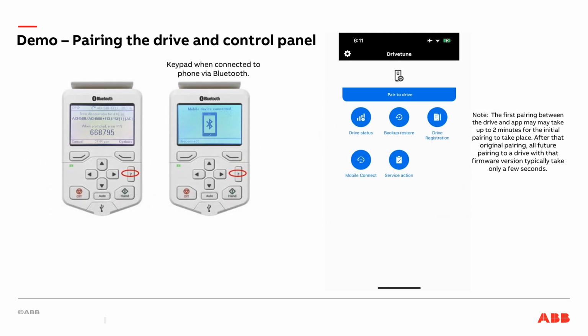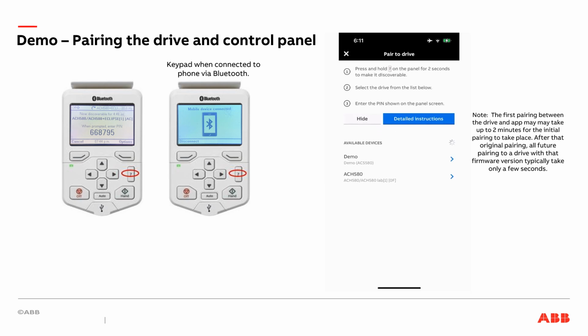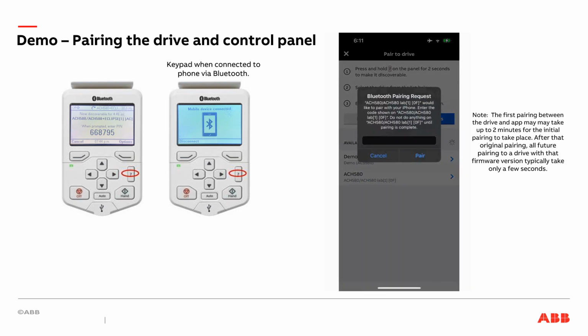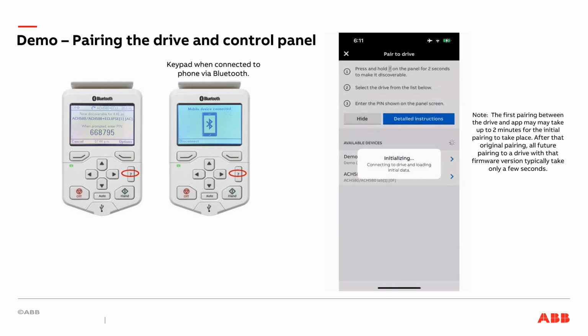After activating Bluetooth on the drive, open the app, select Pair to Drive. This will bring up a list of drives. Select your drive, then enter the 6-digit PIN that was provided on the drive's control panel, and select the Pair button. The app and the drive are now initializing the connection and sharing the drive's data. This will take a few moments to establish the connection.